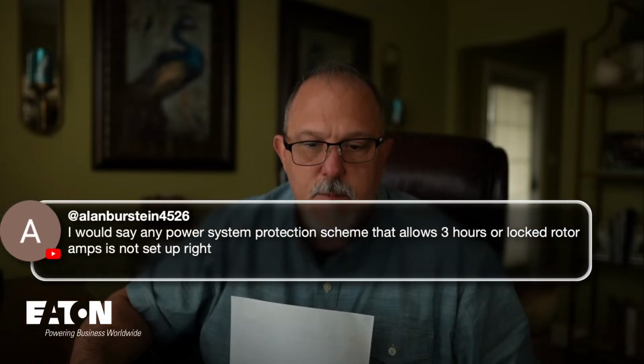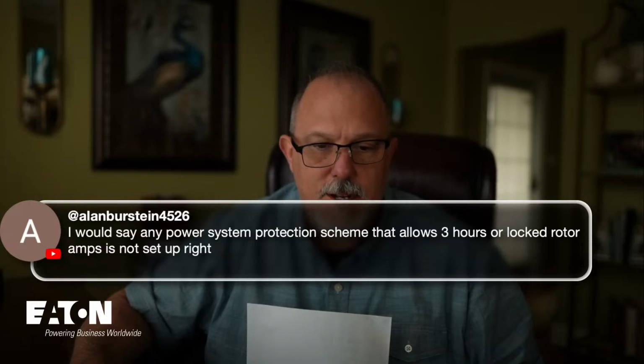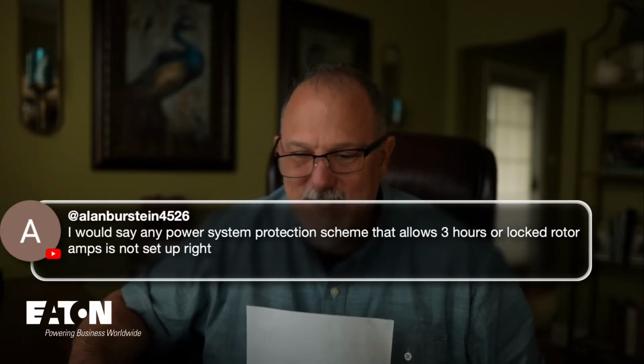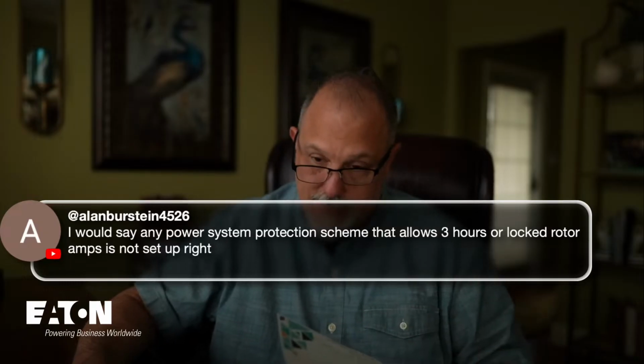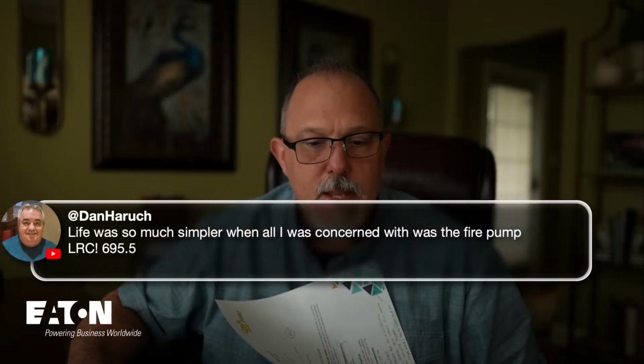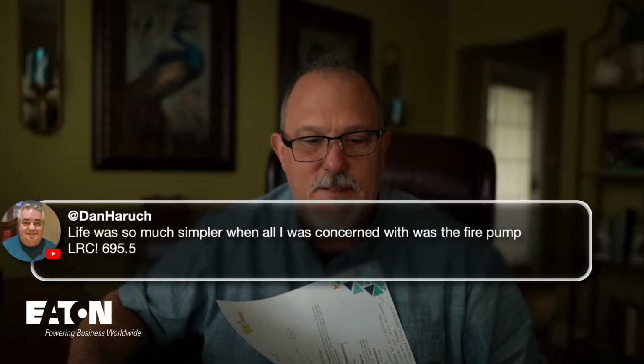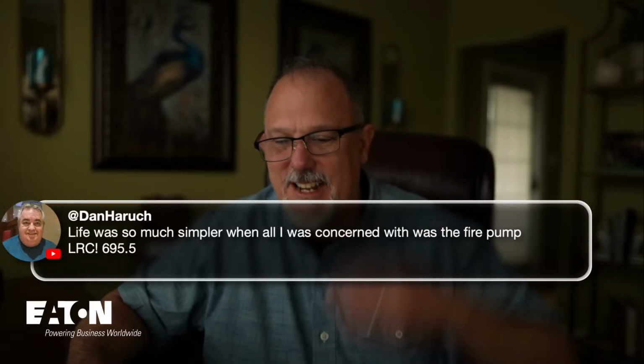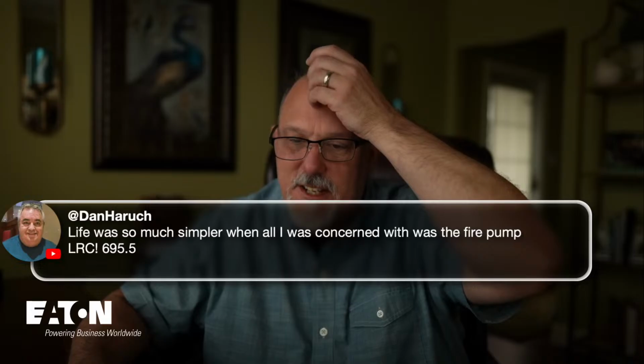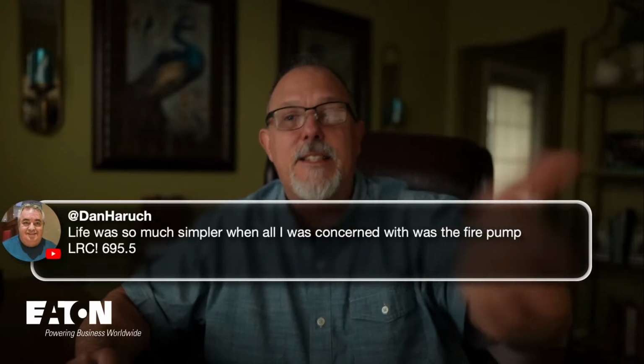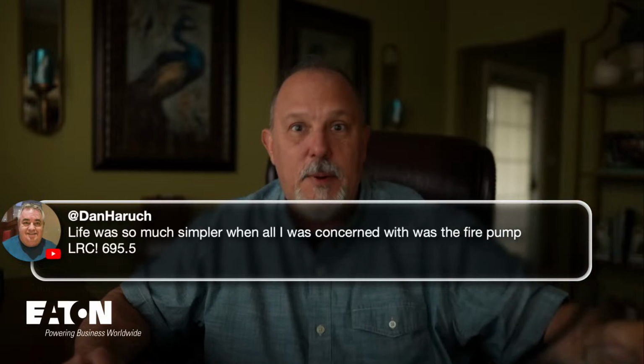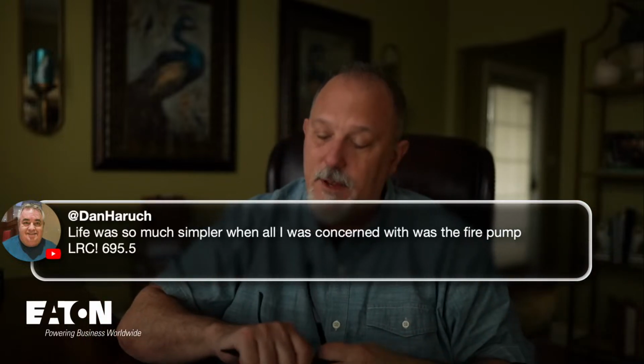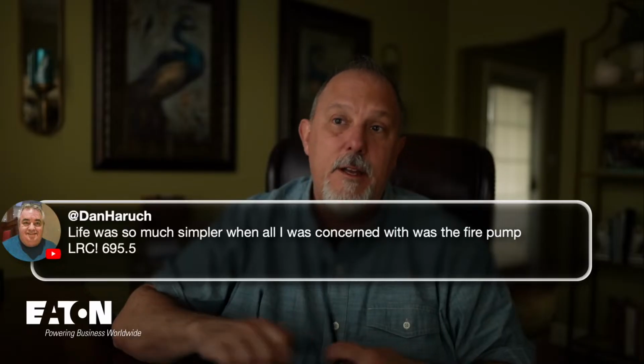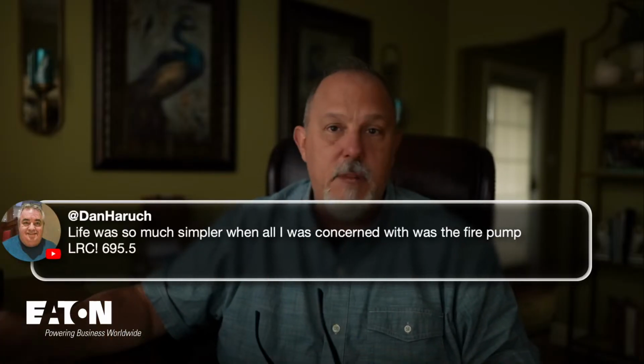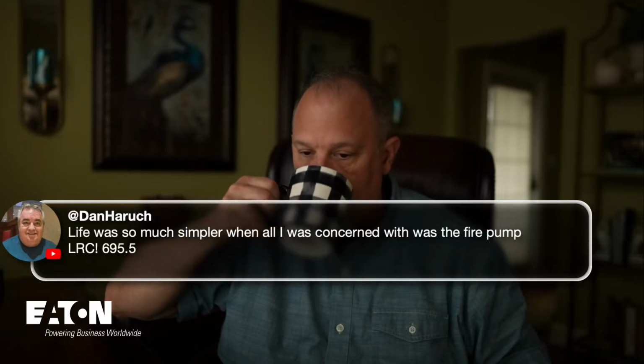I would say that any power system protection scheme that allows 3 hours of locked rotor amps is not set up right. You know what, Alan? I didn't want to say it, but you said it, and I'm with you. LRA. Life was so much simpler when all I was concerned with the fire pump. Locked rotor current 695.5. Yeah, life was so much simpler. And that's, you know what, Dan? That's a good point, that for a fire pump, I have to assume, remember, I want that fire pump to be pumping water. I don't care if I melt the motor and melt everything else around it.